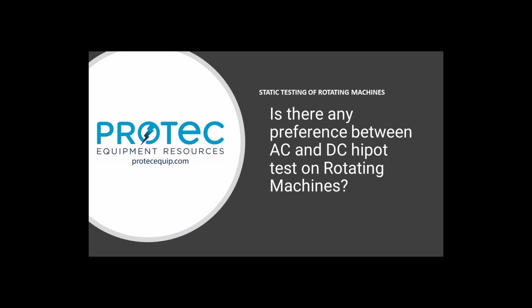Well, as you noticed, Matt, throughout the presentation, particularly when we're quoting from the various IEEEs, DC dominates in this field. The insulation resistance test is a DC test. The testing of high potential is all done at direct current. So when we really looked at almost all the static tests that we cover today and all of the references to IEEE, it's all been DC.